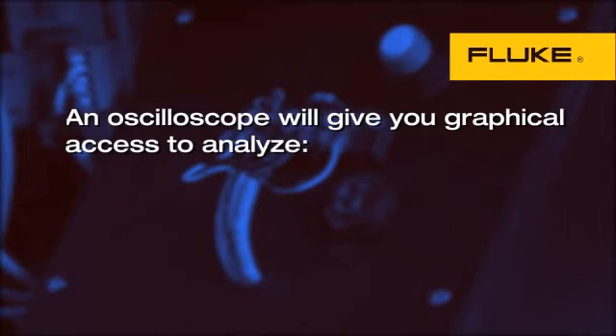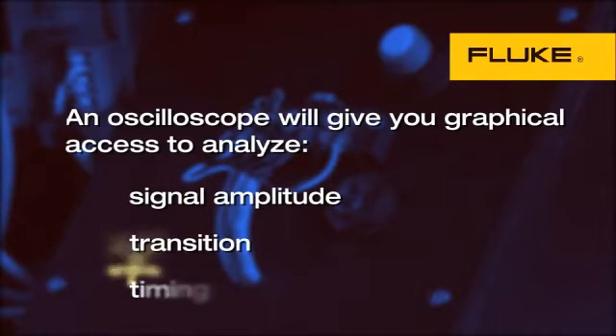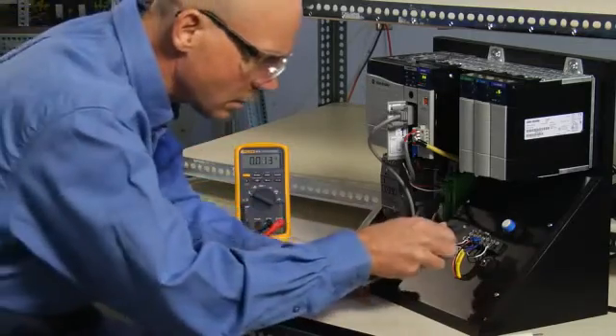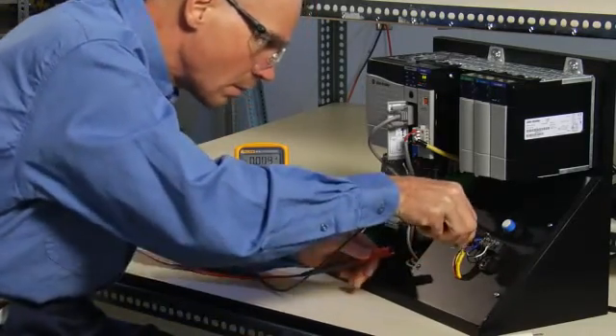An oscilloscope will save you hours of trial and error by giving you graphical access to analyze signal amplitude, transition, and time relationship details. In our example, a proximity switch is causing erratic operation in a parts sorting system.